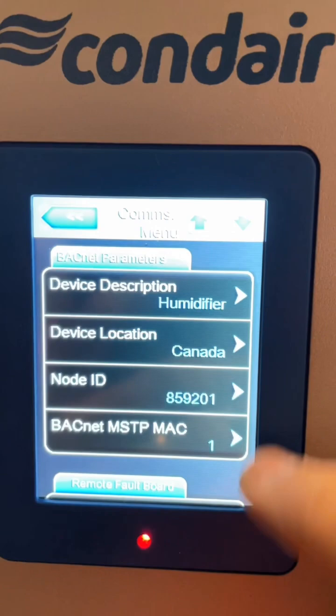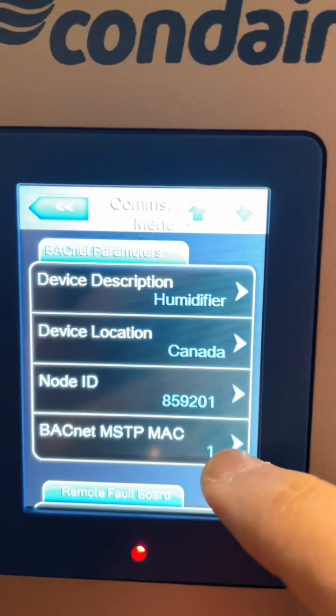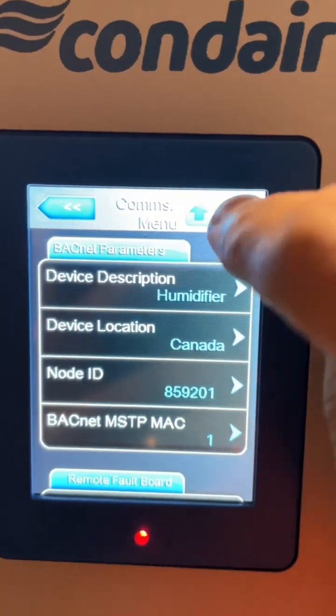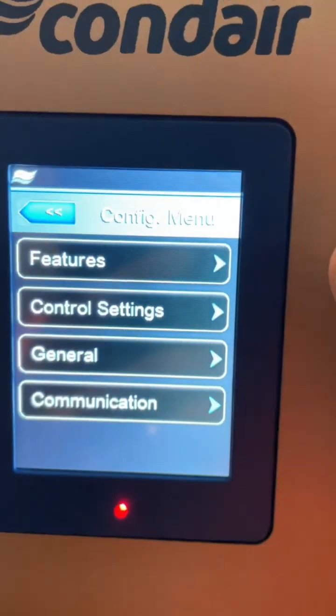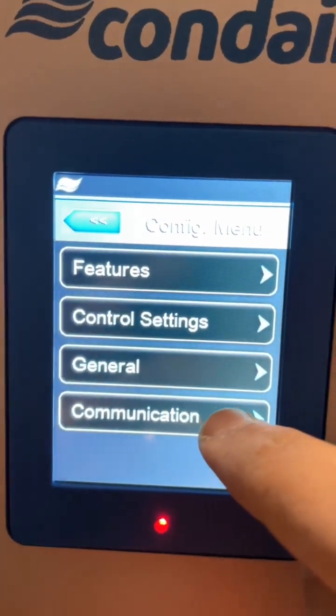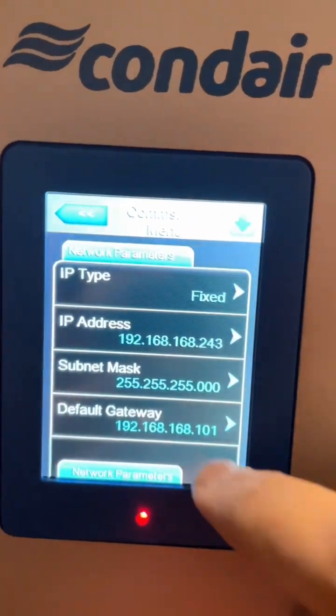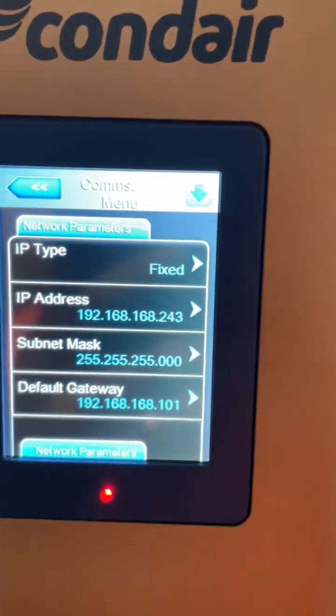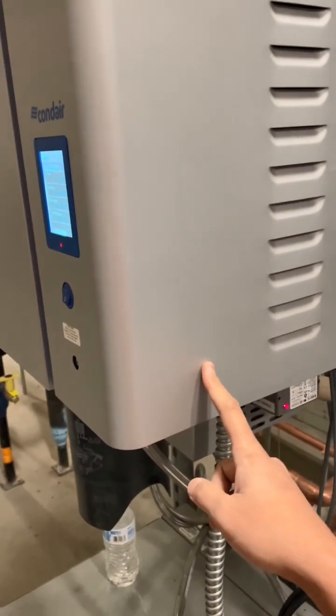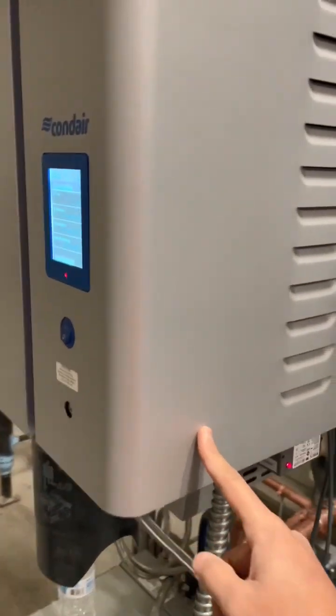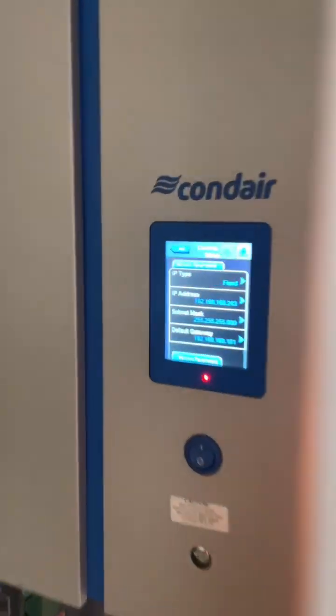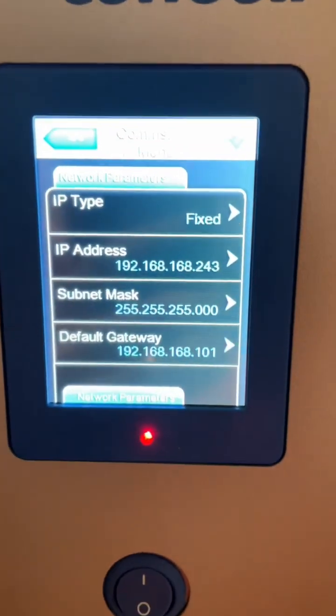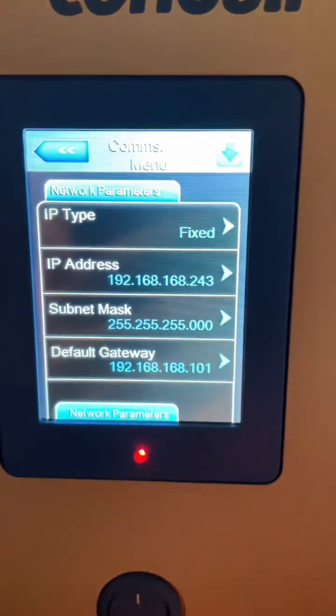What you see is going to be your device instance. The MAC address is your MAC here. Now if you want to do BACnet IP, you can change your network parameters here — they have a network port right behind on this one, so you can connect to it and set up the whole thing. If not, you can do it from this menu right here.